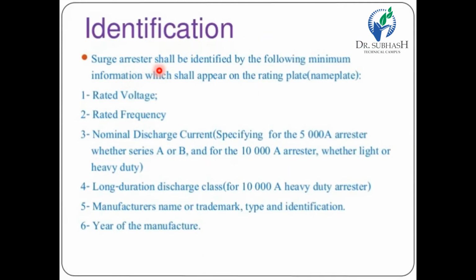Identification. Surge arrestor shall be identified by the following minimum information which shall appear on the rating plate or nameplate. One is rated voltage, rated frequency, then nominal discharge current, specifying for the 5000 ampere arrestor whether series A or B, and for 10,000 ampere arrestor whether light or heavy duty. Long duration discharge class for 10,000 ampere heavy duty arrestor. Manufacturer's name or trademark, type and identification, and year of the manufacture. So these are the topics we can identify the arrestor.